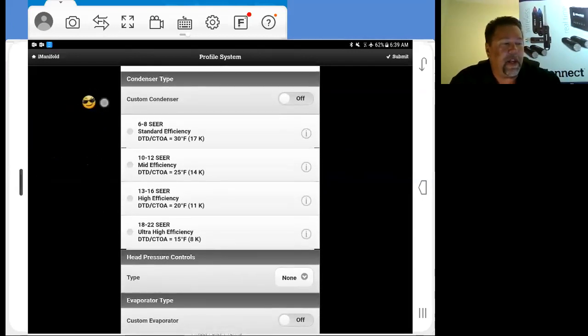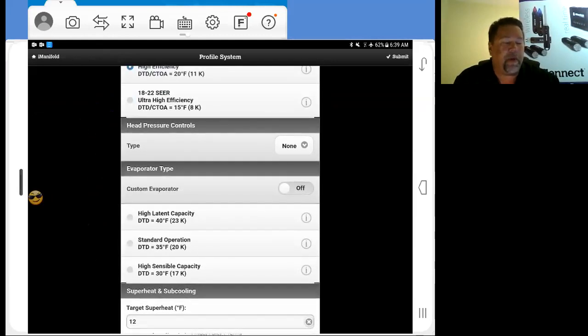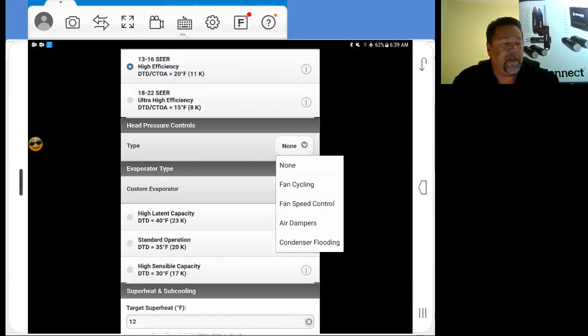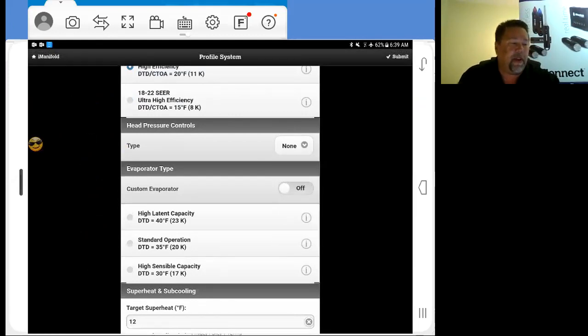Condenser type, custom condenser, we use that for low temp situations because their design temperature differentials could be a lot different from what we have here. But on our standards here, 6 to 8, 10 to 12, 13 to 16, 18 to 22 SEER. We'll use our high efficiency 13 to 16 SEER. There are no head pressure controls on AC and heat pumps. If you did select a refrigeration profile, you've got fan cycling, speed control, air dampers, and condenser flooding controls. But we've got nothing on that.